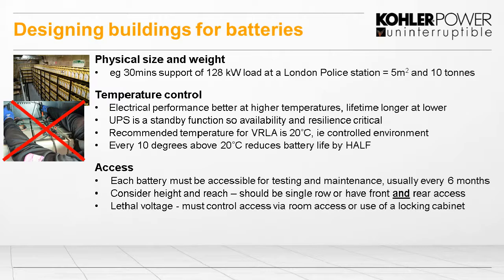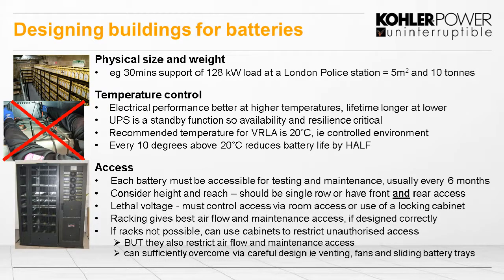So we can either mount them on a rack, as you see from the top picture, and this gives us good maintenance and good airflow. However, there might be a restriction that we have to make sure they're protected against people rubbing by them and touching them. So we have also the option of cabinets, but there's always compromise either way you do this. With cabinets, there can be a restriction in airflow and maintenance access, but we can mostly overcome this with good design when we put these in.